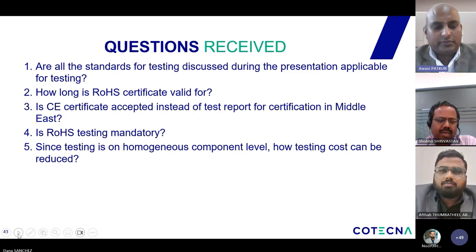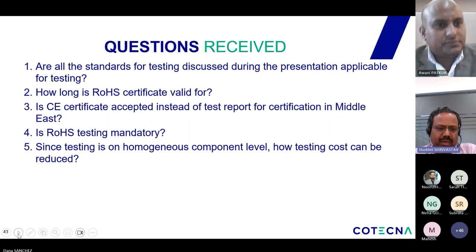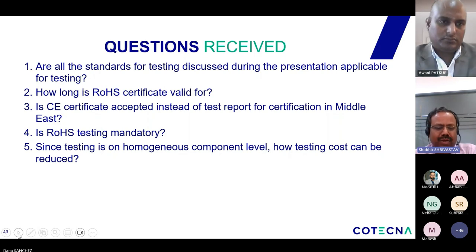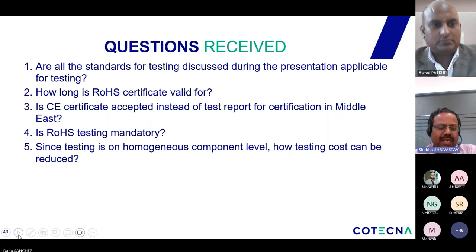So now, yes, Dr. Shobhit. One more thing I would like to add to what Aftab said. If the limit is 1000 ppm and the result is between 700 and 1300 ppm, then you need to go for wet analysis to draw the final conclusion. And if it is more than 1300 ppm, then it can simply be said that it is non-compliant. This is for lead, cadmium, mercury.